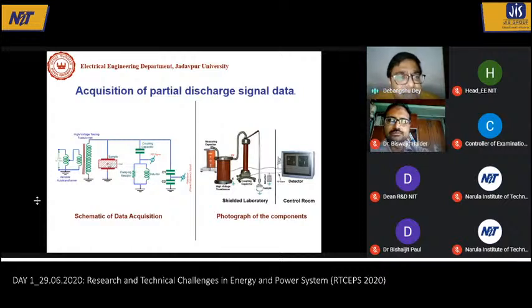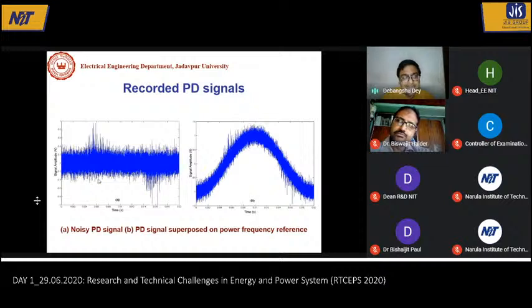In case of practical use, that will be a real life equipment. So within the sample there exists some void, and due to the void there will be some discharge, and that discharge will create some electromagnetic pulsation, and that electromagnetic signal will be captured by this network, and that will be recorded. What sort of signal we can get, I can show you in this diagram.